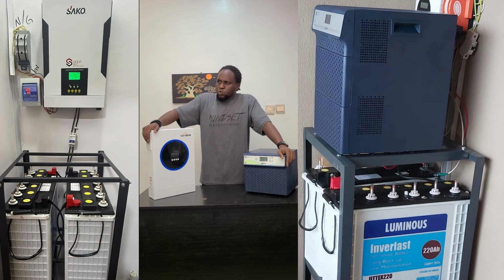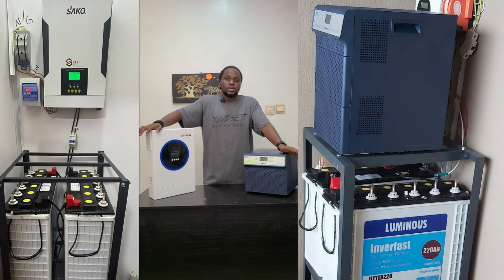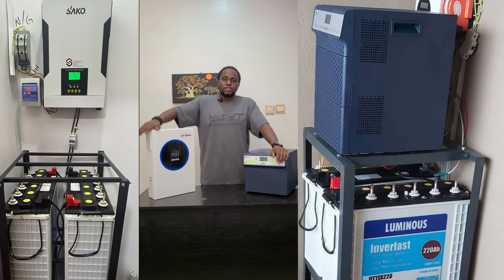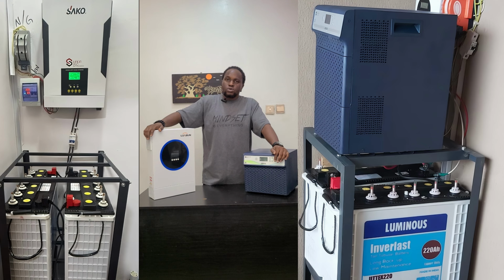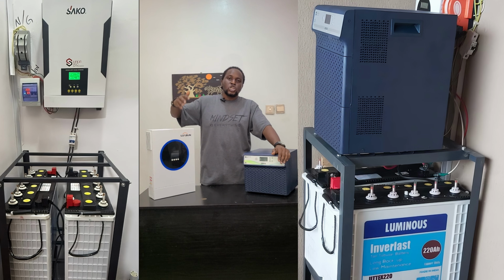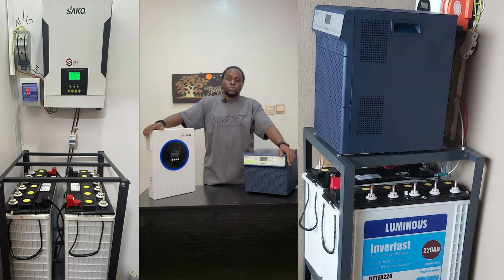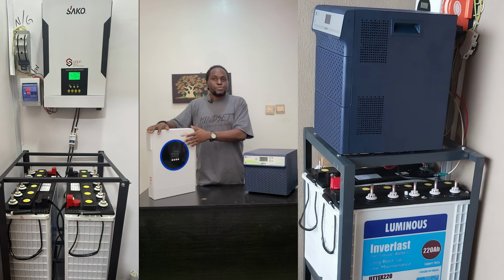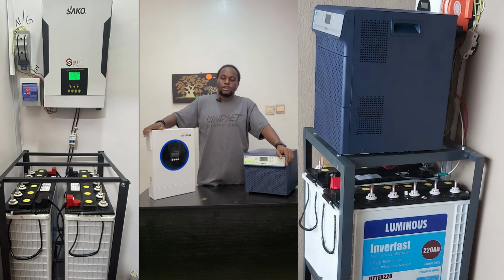For example, if the load in the house is 2000 watts and the sun is just coming up and giving maybe only 500 watts, what this guy will do is take that 500 watts from the sun, combine it with the balance of 1500 watts from the grid, and supply it to the house. As the sun increases in intensity, it will adjust itself and take the shortfall from the grid. So if the sun increases to 1500 watts, it will take 1.5 kilowatts from the sun and only 500 watts from the grid and supply it to the home.